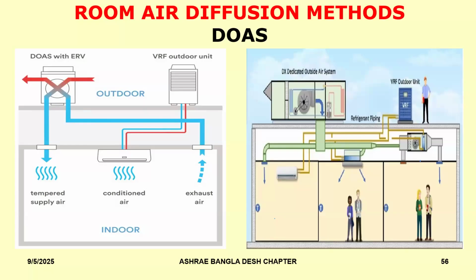So what we do really is to decouple the loads. For example, on the left-hand side, you will see a simple example of one zone where we have an outdoor unit and an indoor unit. This is simply, like you have a split unit, taking care of the space sensible load. And then you have an outside unit which is bringing in the tempered supply air from outside. Okay, this is the outside air, and then there is an exhaust air.